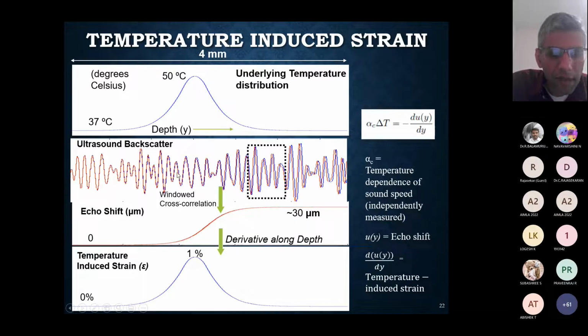So it's a cumulative effect. If I apply standard signal processing methods, in this case we applied a windowed cross correlation. We break the echo into multiple windows, and in each window we try to cross correlate the red waveform with the blue, then reconstruct the echo shift profile. It will basically look like a sigmoid shape — this is your raw displacement profile. Based on the echo shifts, you can extract that, and it will have this shape.